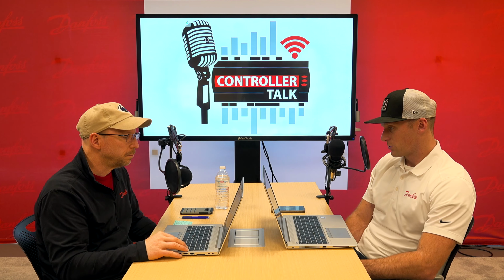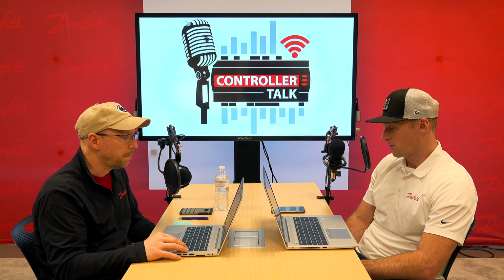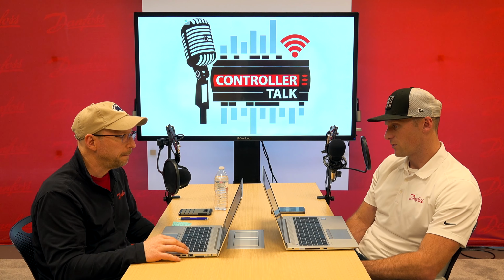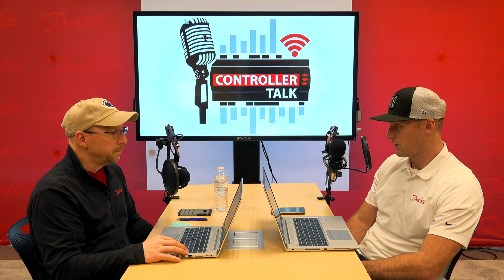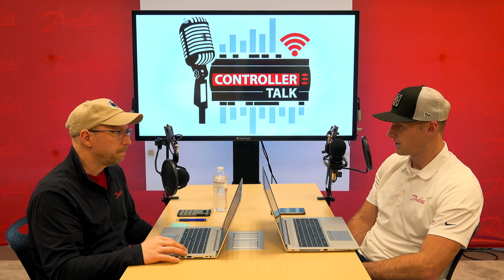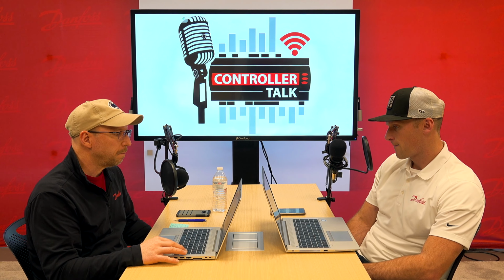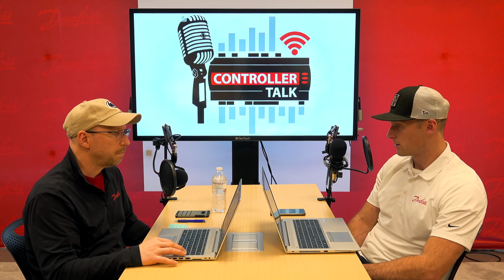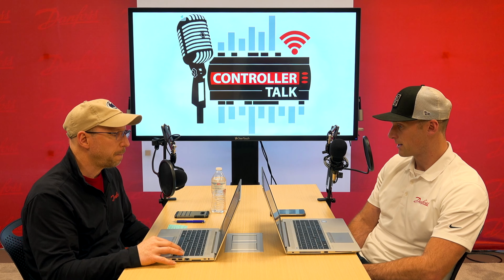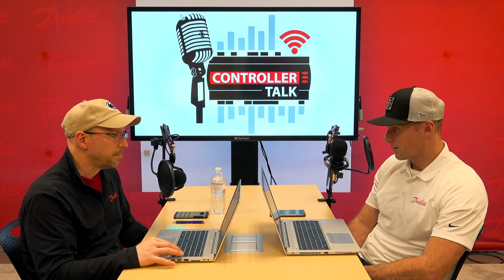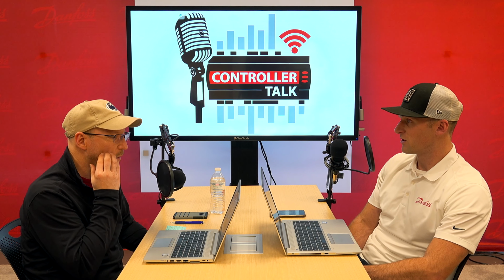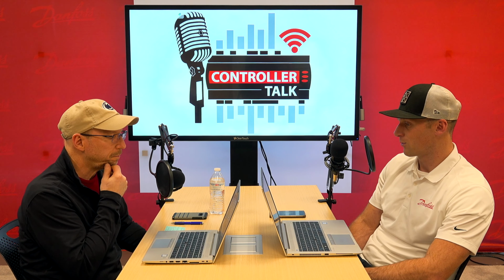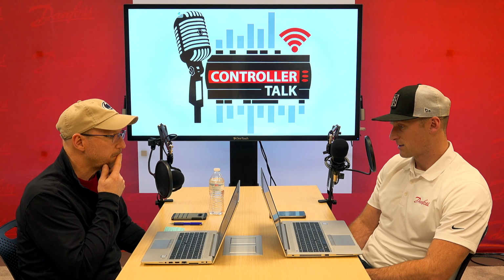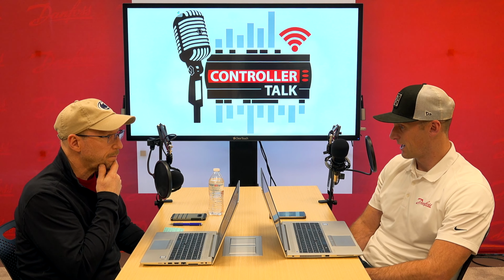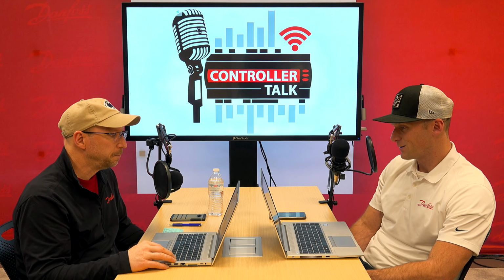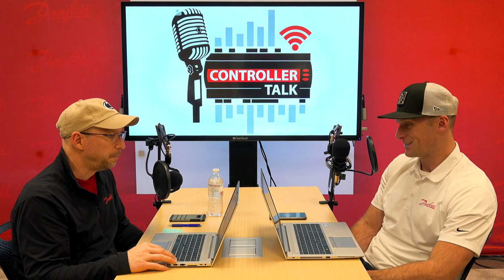IO, case controllers, pack controllers—all these things tie to the system managers today through Modbus or Echelon comm loops for the most part. So you want to review them and make sure everything's wired correctly. We have the termination switches above the Modbus and LAN plugs—those should be in the right state, on for a single comm loop into them, off if you have duplicate or two comm loops coming back to a single plug. As for the type of wire, we've talked extensively with people about using Windy City wire—that's the most common on the market, but for Echelon 485 and Modbus, we're talking about an EIA 485 rated cable, so you don't want to use old thermostat wire or anything you picked up off a truck for five dollars.